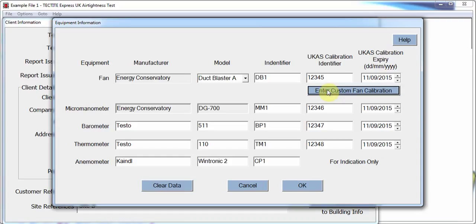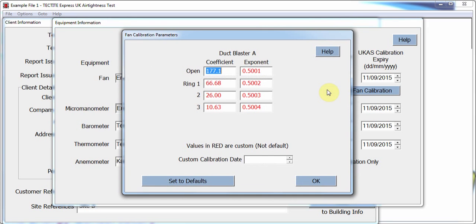The calibration expiry date will be compared against the test date, and where the equipment is found to be out of calibration, this will be recorded as a deviation in the deviations page of the software. By selecting Enter Custom Fan Calibration, the user can enter the calibration coefficients from the last UKAS calibration. The software is provided with generic calibration coefficients — these must be changed to those obtained at the last calibration, or a deviation will be reported.